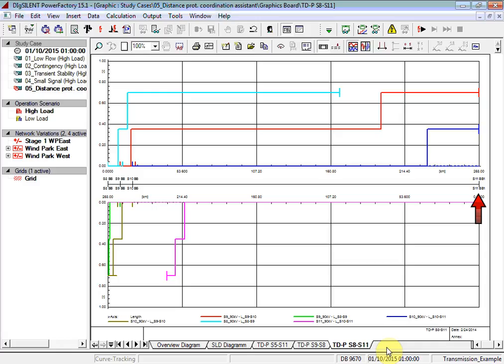The lower diagram illustrates tripping times for power flows from the right-hand side of the diagram towards the left-hand side of the diagram, i.e. from substation 11 towards substation 8. Focusing on the upper diagram, let's consider what will happen for a fault 50% along the conductor between substation 10 and substation 11.